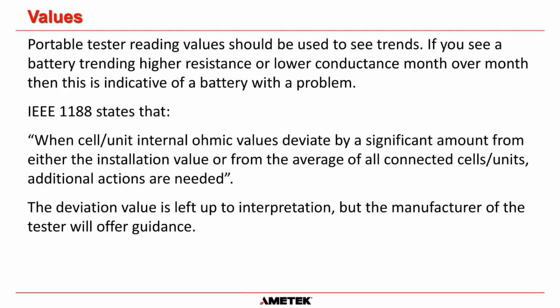Portable tester reading values can only be used to see trends. If you haven't got a baseline and you measure a battery, you have no idea what you're looking for. So when you start to use a tester and compare it to a baseline, you have to see the battery trending higher for resistance or lower for conductance month over month. Then that is indicative that the battery is starting to have a problem.